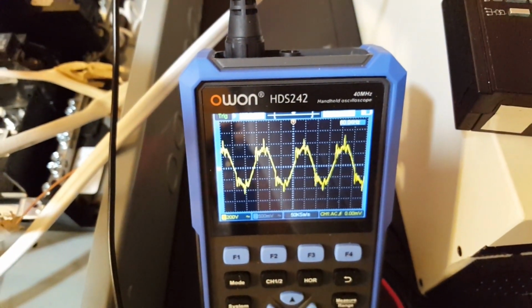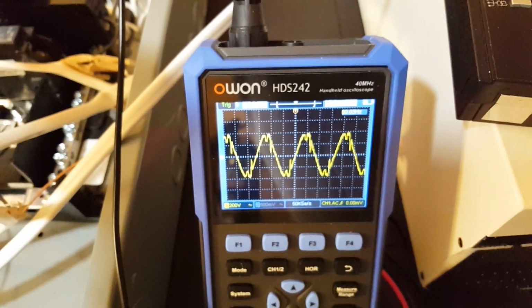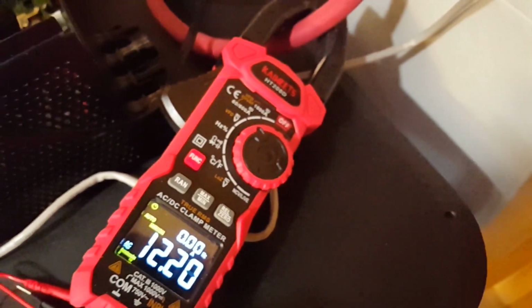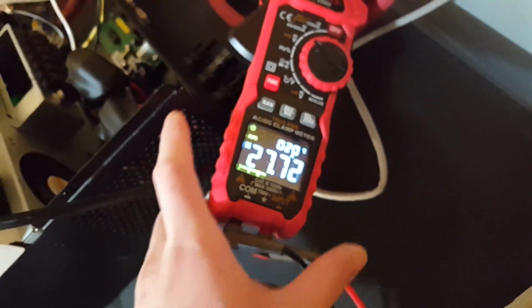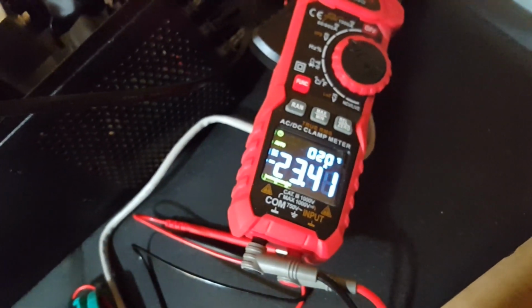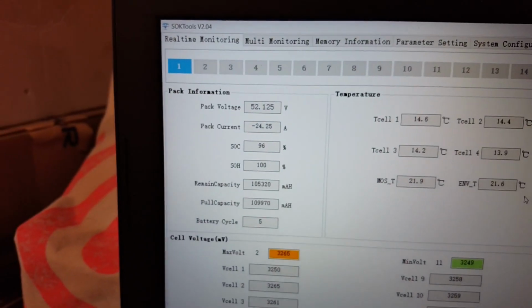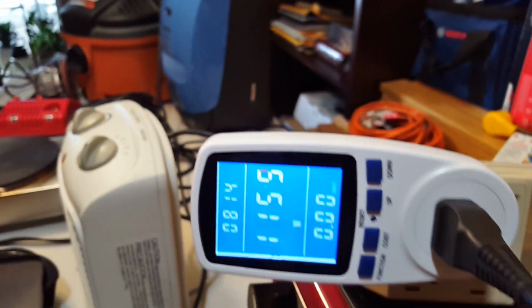Let's check DC inrush for this vacuum cleaner. Go to inrush mode, starting vacuum cleaner. .2 inrush. Running amps is 27.7 on one cable, and it's 23.4 on the second cable. BMS monitoring software says 24 amps discharge, and the pack voltage 52. If you want to know the running watts for that vacuum cleaner, 1155. Okay, now we're getting some serious stuff.